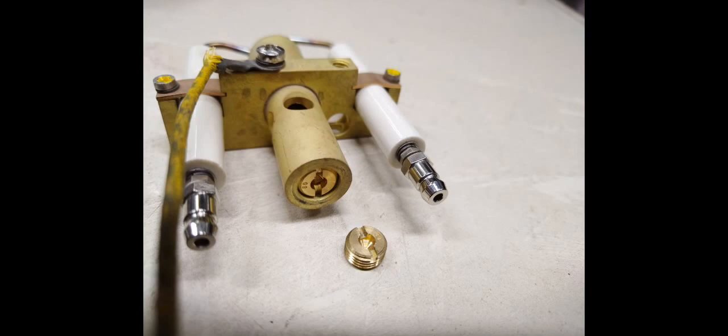So I got that boiler on and had all three boilers lighting. The problem with this boiler, I don't know whether it was that the burner needed cleaning down or if it was the pilot assembly, but when I swapped the pilot assembly round with another unit that was working, then my boiler decided to start working. And then the pilot which I thought was faulty that I put on the boiler that was working, that also worked. So basically I had only two boilers working and one not working when I arrived on site, and then when I'd finished, I had three operating. That was just by cleaning the burner out and swapping the pilot assemblies round. I don't know if something wasn't connected properly, like the earth connection wasn't on properly, or one of these connections here, the spark or the detection, or if the pilot tube had some blockage, or if the unit just needed purging for a very long time.